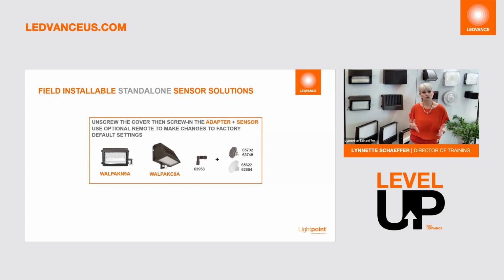Now, of course, standalone control solutions are pre-programmed at the factory, but those settings can be changed via a remote, which is sold separately. So as you can see here in the photo, you have a little bracket. That bracket attaches to the knockout, one of the knockouts that have a plug. You basically plug it in, you attach your control solution, and that's as easy as it is. The bracket's nice because you can move it and rotate it so that you can get that sensor to be exactly where you want it to be.